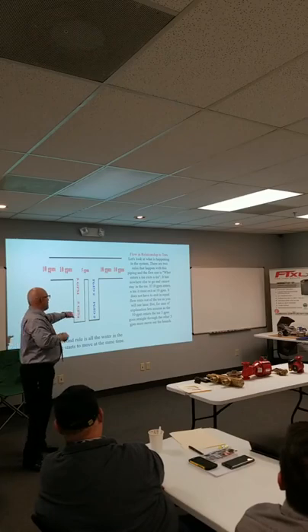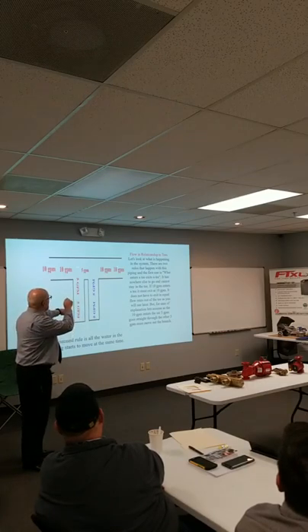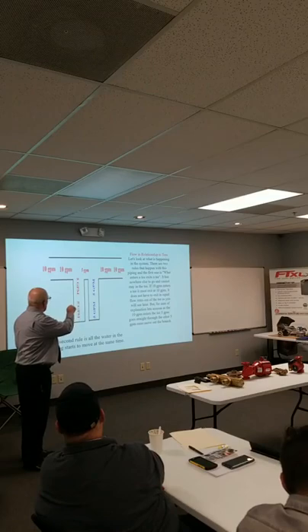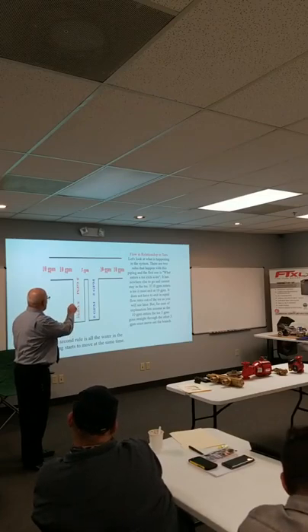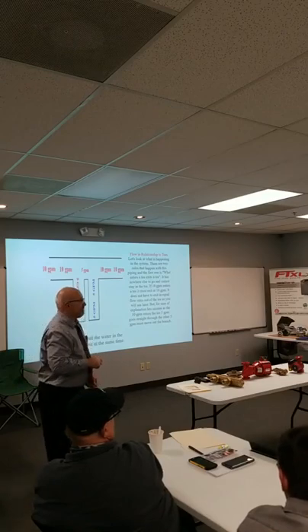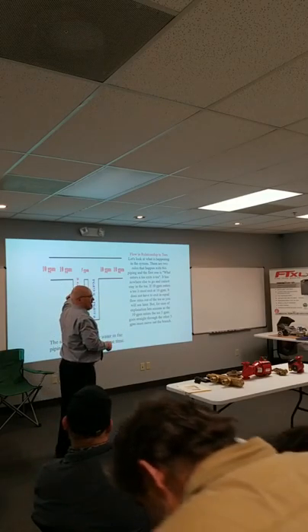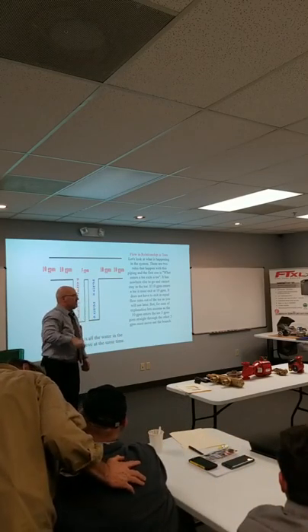It's a boiler. Yeah. So we're going to take our return from the system, our primary loop, and go to our secondary loop boiler. This is the colder water coming in. We're going to heat the water, and it's going to go back here. And if I take 5 out, what goes into a tee must come out of a tee. So I got 5 in between those tees. So you're tempering it 50-50 when you're reaching water in this pipe. Exactly. And I'm injecting heat, so to speak. By getting a colder supply temp, you get a colder return temp. You get more efficiency out of it.